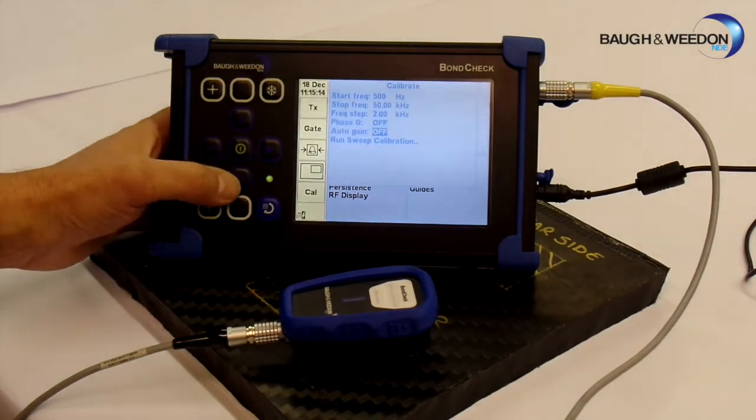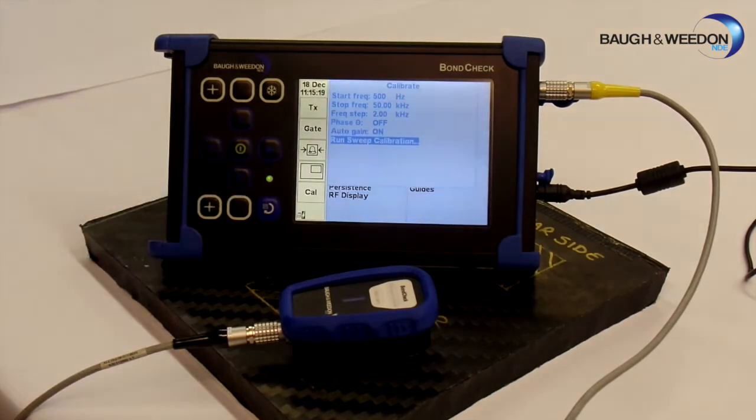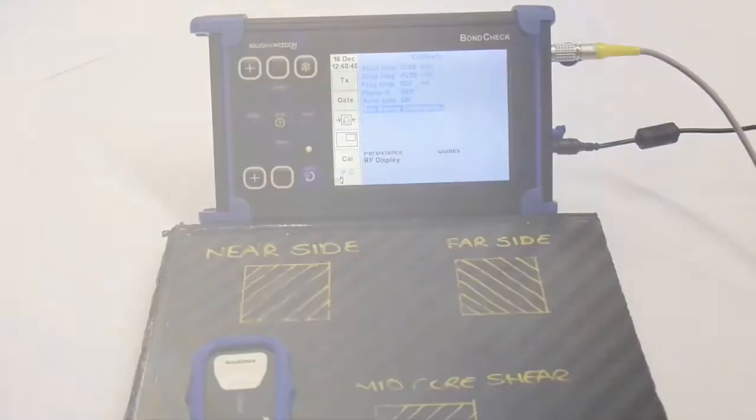So now go down to auto gain, which I am going to turn on, and come out of that, and now go down to run sweep calibration. We are now ready to run the actual calibration prior to carrying out the inspection.